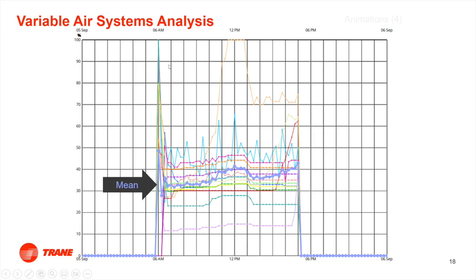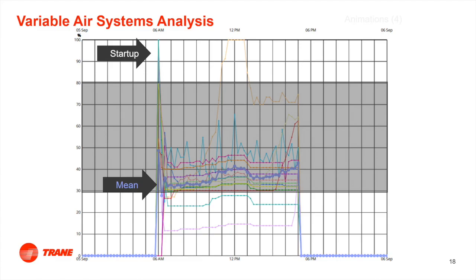You can see this huge spike on startup too, can't you? Now we're looking at all the VAV boxes—they spike when they start, they all start at the same time. But when they come down to normal, they're about 30-35% open. There's that startup peak, and here is the happy spot.